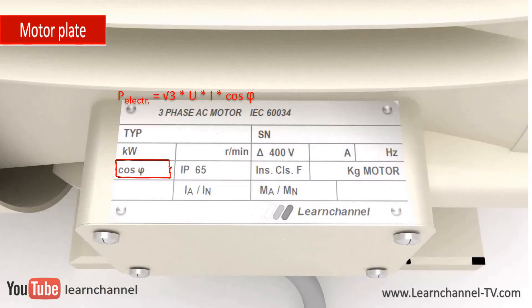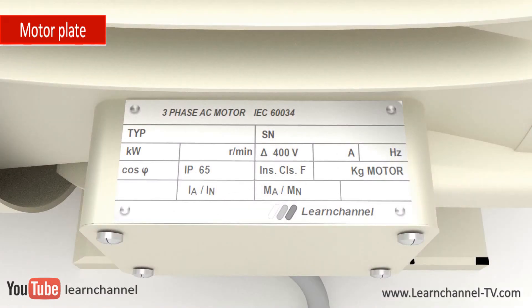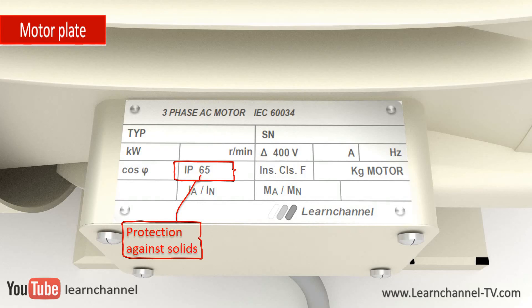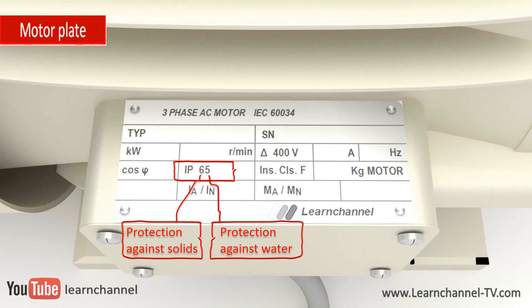The insulation class describes the thermal tolerance of the motor windings. The letter indicates the motor windings' ability to withstand operating temperatures for a specific length of time. Motors controlled by a variable frequency drive usually must have a higher insulation class. Ingress protection codes define how well an enclosure protects against the external environment. As the number gets higher, the protection gets better. The first digit defines the protection level against solids, the second against liquids. You must use both digits to define an enclosure. Further information about your motor you get from the datasheet.